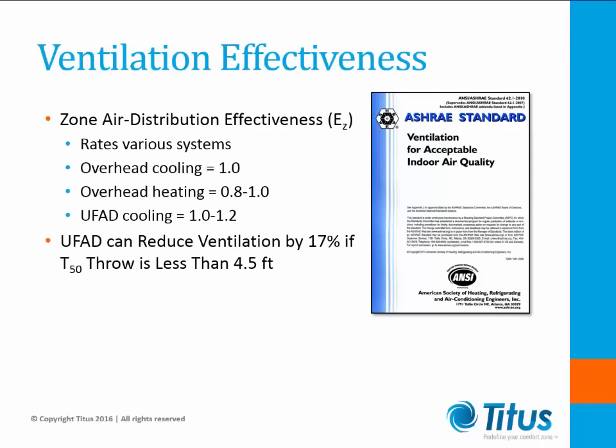ASHRAE Standard 62.1 also rates various types of air distribution systems with respect to Zone Air Distribution Effectiveness, or EZ. Ventilation air is only effective if it reaches the breathing zone of the occupants. Therefore, systems can be rated for ventilation effectiveness based on the location of the outlets, the returns, and the temperature of the supply air. Table 6.2.2.2 in the standard provides EZ values for various systems and conditions. For instance, supplying cool air from the ceiling has an EZ value of 1.